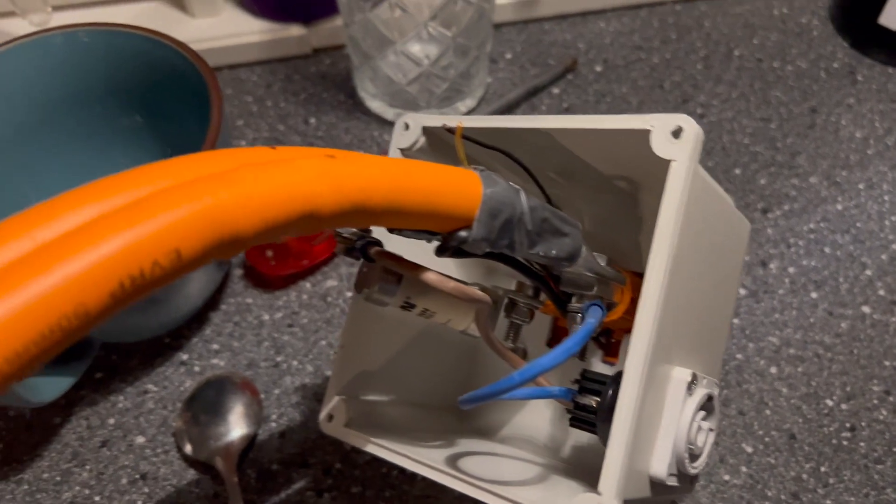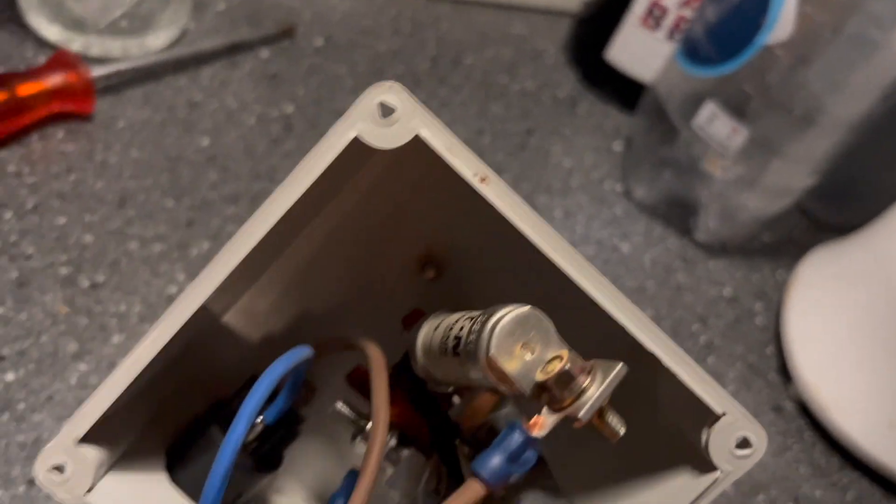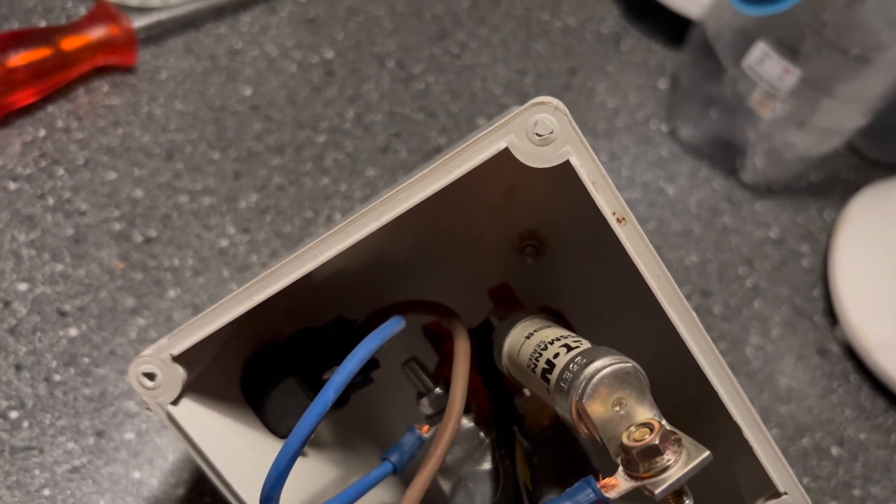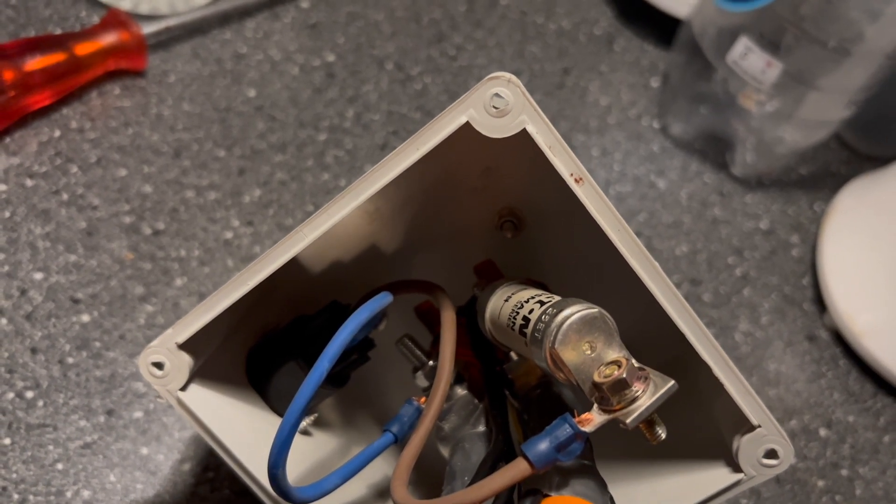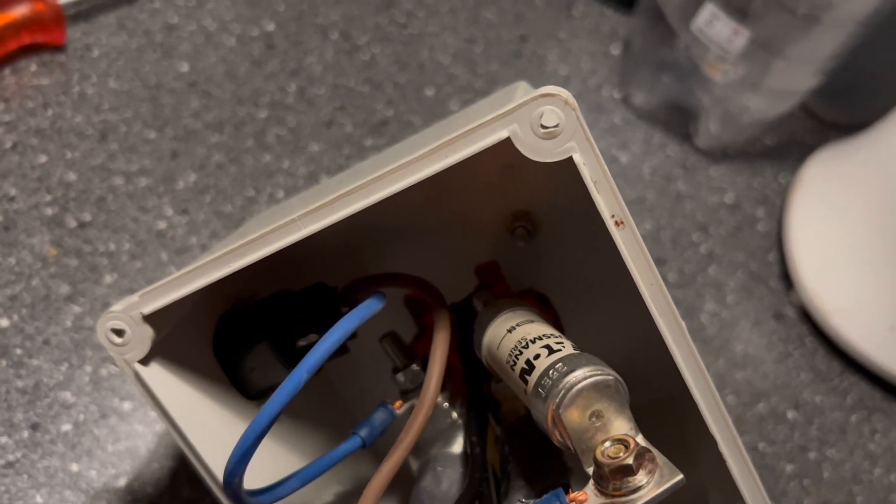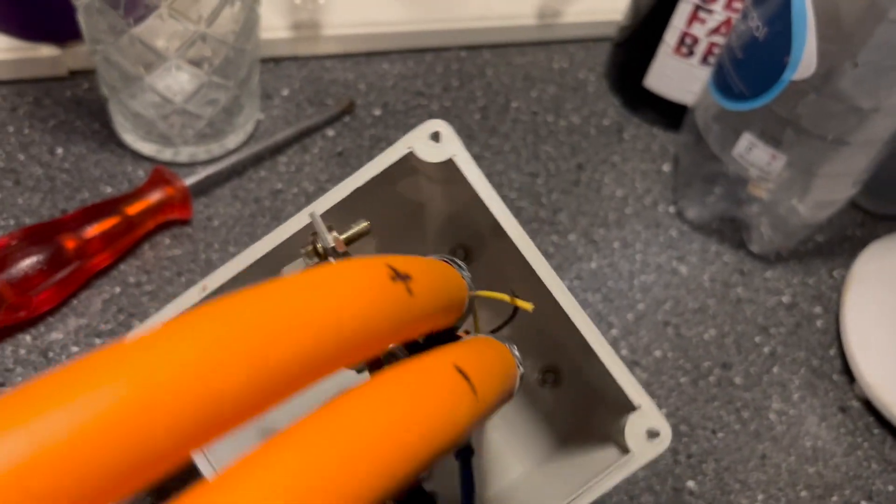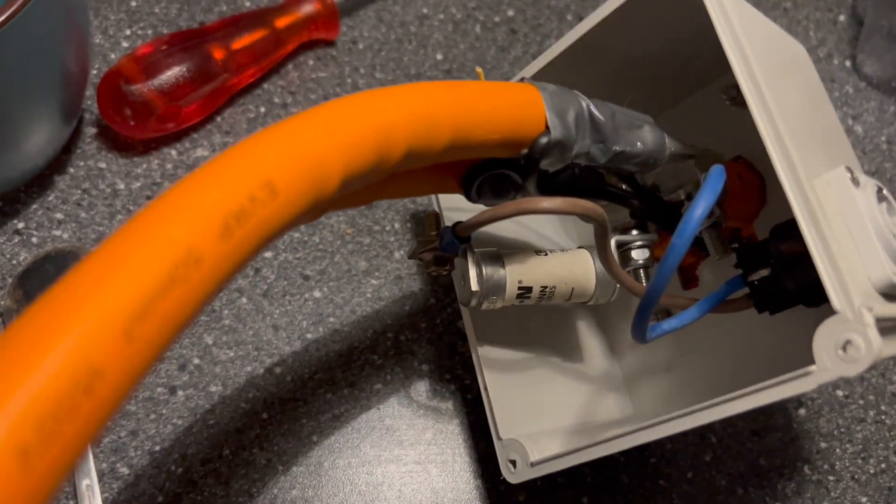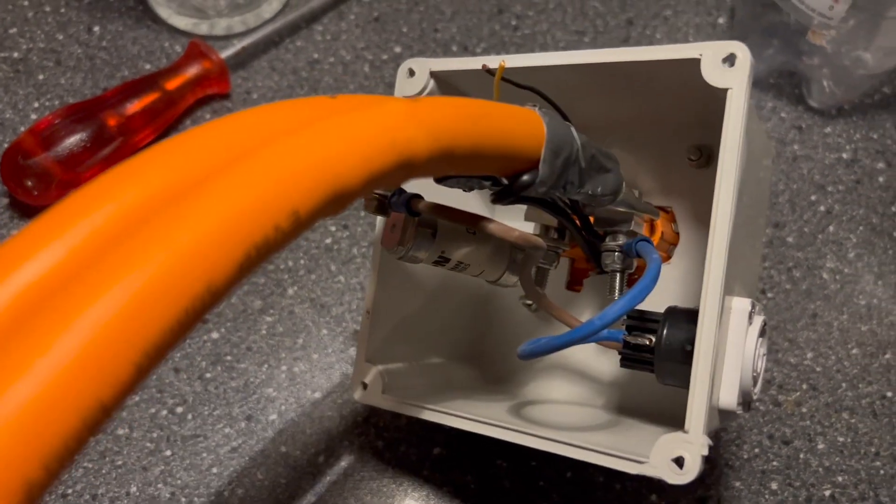2.5 mil cables inside. Like I said, the fuse is only to protect shorts. This particular fuse will have a very large gap when it's stripped, and there will be no sparks flying inside there because it's filled with sand and fully ceramic. A way better solution for the purpose.